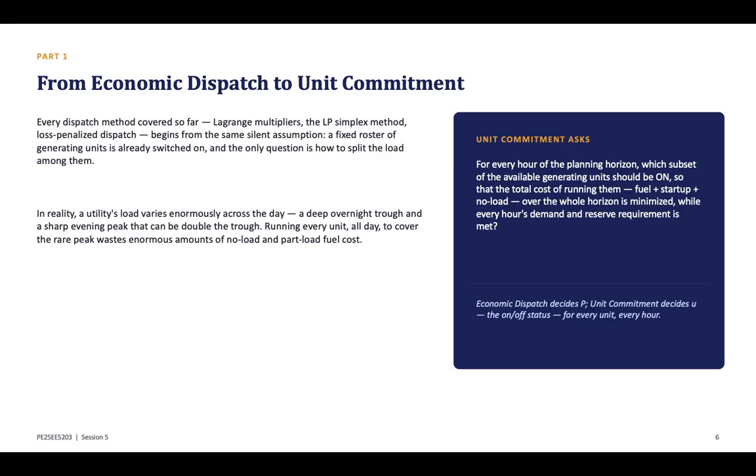Economic dispatch searches inside a continuous region defined by generator limits and power balance. Unit commitment first chooses among many disconnected continuous regions, one region for each feasible on-off combination. After a state is selected, economic dispatch searches inside that state's continuous region. The full UC problem is therefore a collection of continuous dispatch problems connected by discrete transitions over time.